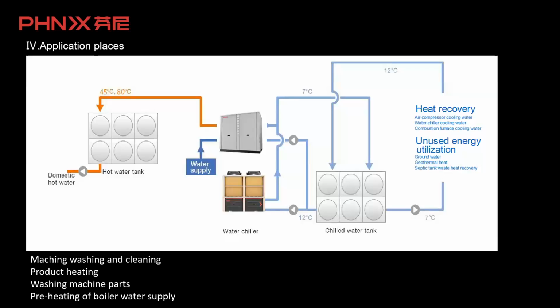So the following is the application. From this part, you can see the water-to-water heat pump is working together with the water chiller. On the right side is for heat recovery and unused energy utilization. On the left side, the hot water range is from 45 degrees to 80 degrees. The maximum outlet water temperature is 80 degrees, and it is usually used in machine washing and cleaning, product heating, washing machine parts, and preheating of boiler water supply.